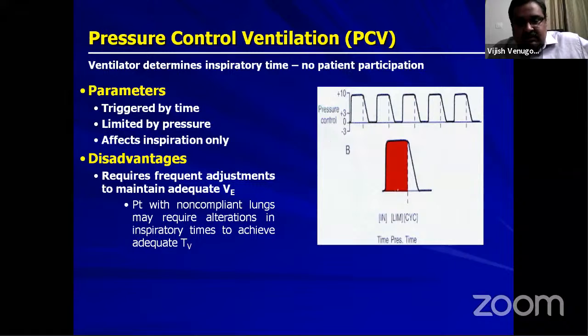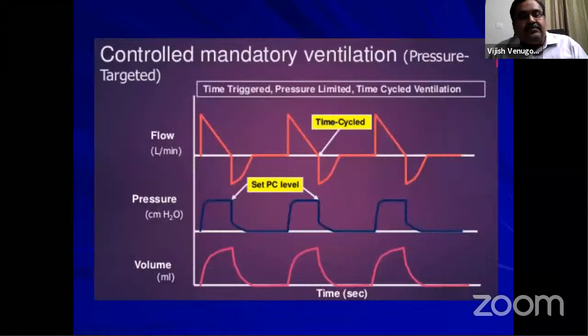The disadvantage is it requires frequent adjustments to maintain adequate expiratory minute ventilation. So patients with non-compliant lungs may require alterations in inspiratory times to achieve adequate tidal volume. So here only the pressure is applied, and depending on the compliance, the tidal volume will change. So it is very important that we monitor the tidal volume for a patient who is on pressure control ventilation.